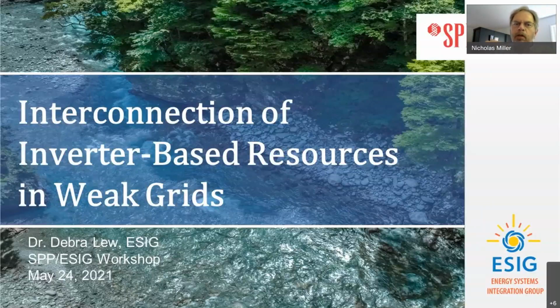People talk about virtual synchronous machines - just make it look like a synchronous machine. But synchronous machines have 3 or 4 per unit short-term current rating; that ain't happening, the economics won't drive inverter ratings that high. So part of the investigation is how much current rating you really need, because that turns into a cost term. We're probably not talking about doubling the cost - probably talking more than noise, but not double.